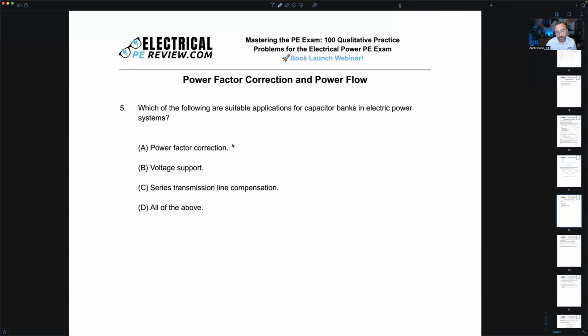So power factor correction is one of the applications. Any guesses on voltage support? So in addition to reactive power, what do capacitor banks supply? They are capacitive loads, and they supply capacitive current. Now, most systems are going to be lagging, right? The only time we really have leading loads is if we have capacitors, which we're usually using to correct the system, or if we have overexcited synchronous motors, which are pretty rare, right? Even in a big facility that does have those, you don't typically have a lot of them. They're very specific types of motors. So voltage support is also a suitable application for capacitor banks.